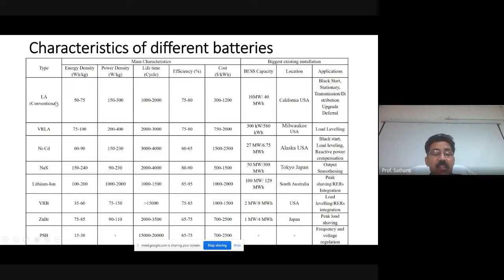For the simplest, most conventional lead acid battery: energy density is around 50 to 75, power density is 150 to 300, and it runs for roughly 1000 to 2000 cycles of charging and discharging, with efficiency around 75 to 80%. Cost is $300 to $1,200 per kilowatt hour depending on size. A battery of 10 megawatt or 40 megawatt-hour capacity is installed in California, USA, in the power system for applications like black start, stationary transmission, distribution upgrade deferral. We'll discuss these applications in upcoming slides.